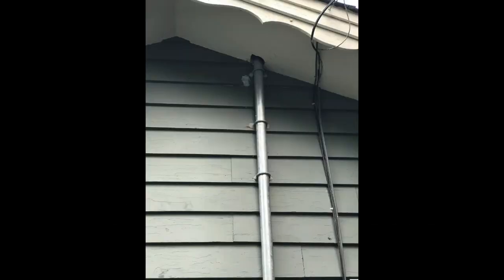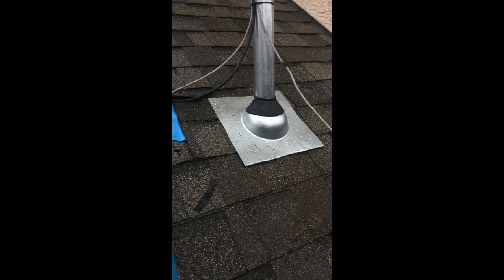In the next part of the slideshow, we will be reviewing a 200 amp overhead service install. With the install of a 200 amp overhead service, a 2-inch mast must be installed. Due to the weight of the 2-inch mast pipe and the support that is required for the hydro lines, U-bolts have to be installed on the mast. These U-bolts must be fastened to the framing of the home for added support. In most cases, the drywall must be removed in order to access the framing of the house for the U-bolts to be fastened. In most cases, the mast pipe goes through the roof of a home and a hole has to be created. We always recommend that the customer hire a roofer to professionally repair the hole after we are completed.